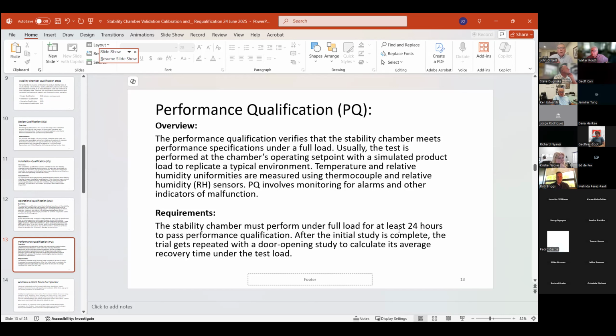Okay. With regard to the door opening and closing, we mentioned that happens in the OQ and gets repeated in the PQ. And I think that's open to some interpretation as well. Maybe perhaps ISPE has done a better job recently in defining exactly how that gets done. But I know that some people will just simply turn their chamber off and watch it go till it goes out of specifications. Others are doing the door opening to see how long it goes out of specifications. There's a couple of different ways that you can do that. I find all that information and that kind of data to be of interest, especially if something happens in the middle of the night, your chamber power goes out, but the door's still closed. You want to know how much time you have to get in there and move chambers around or have a crew fix it.